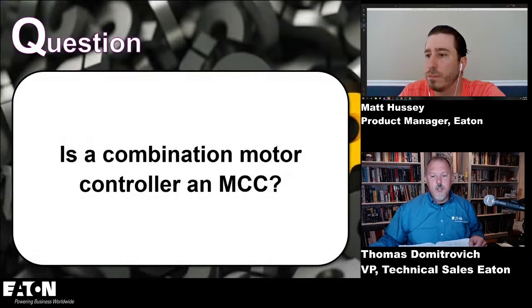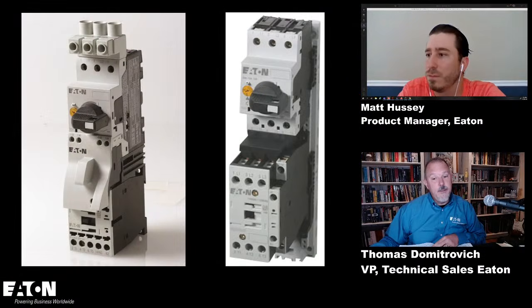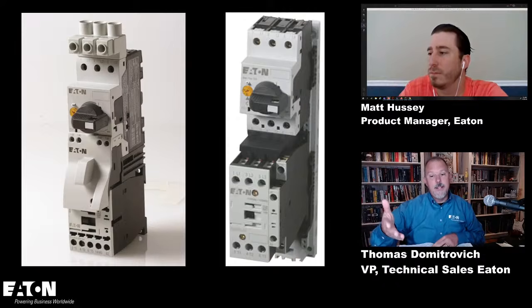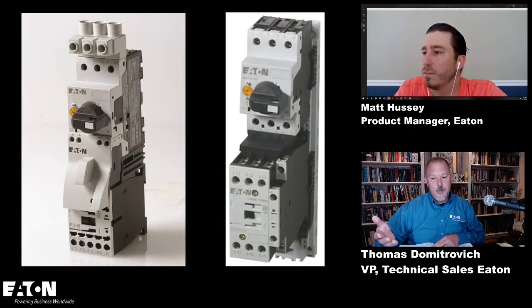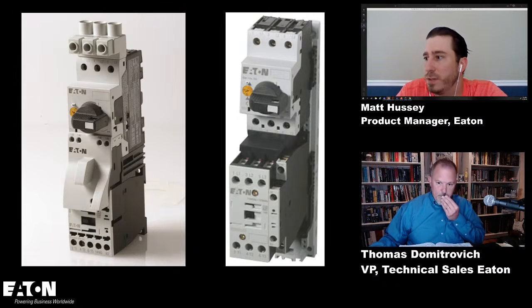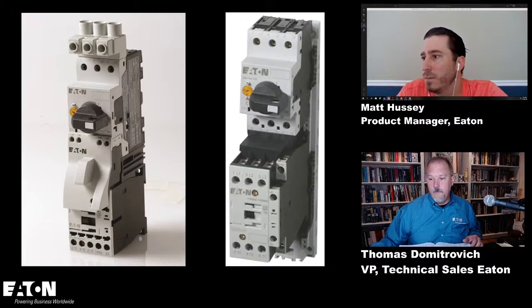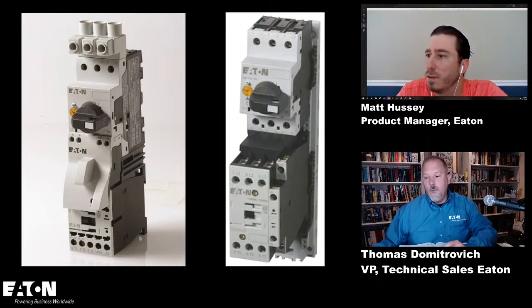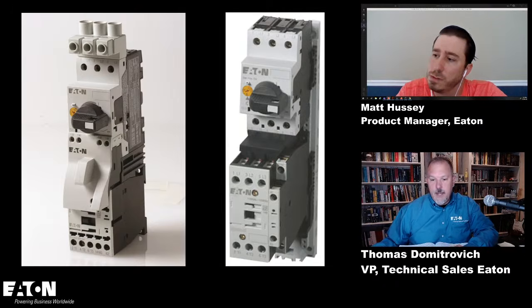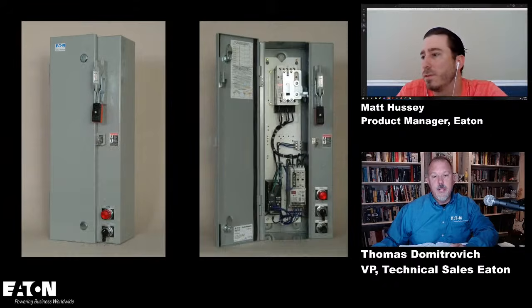All right, combination motor controller, is that an MCC? That's the first question we got of the day. So I put some images in here that pertain to it. That's your combination motor controller. It's got your overload in there and your disconnect, right? Yep, you've got your branch short circuit protective device and your contactor. But I don't think that is what they're talking about. I think they were thinking of something like this, which is your combination motor starter, right?